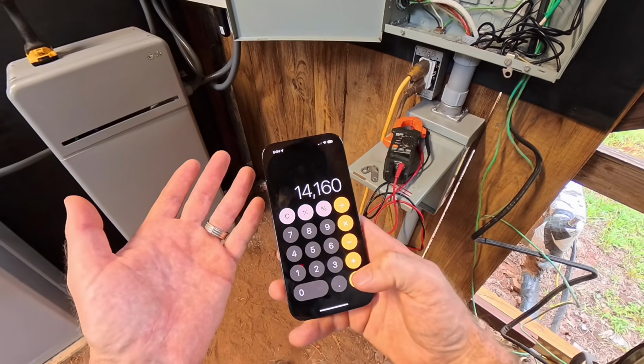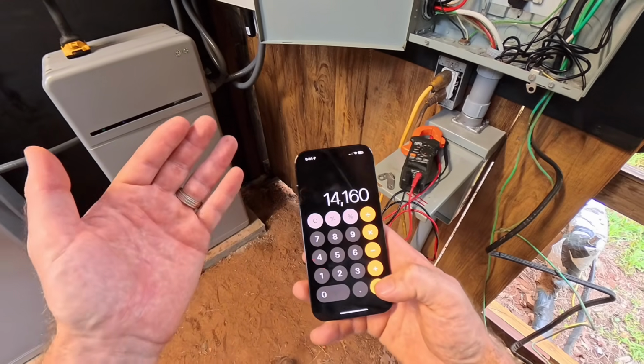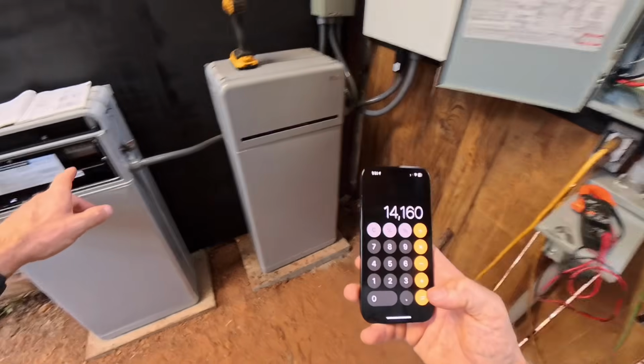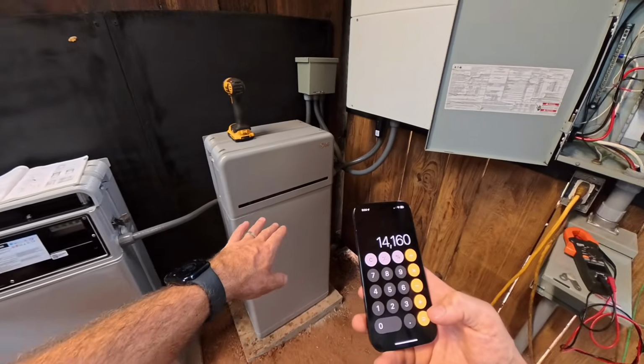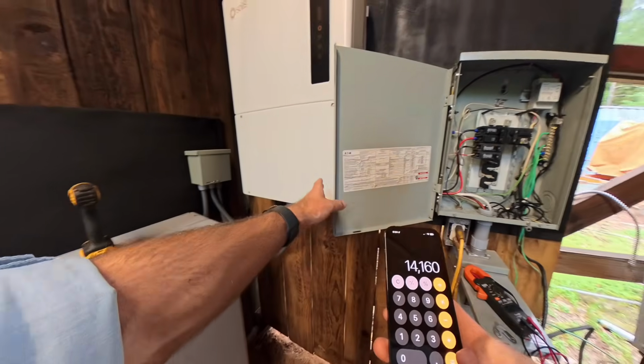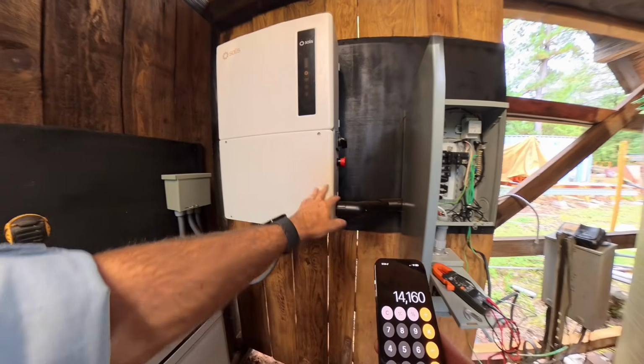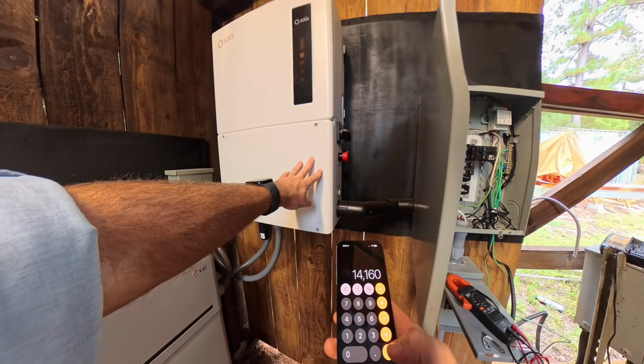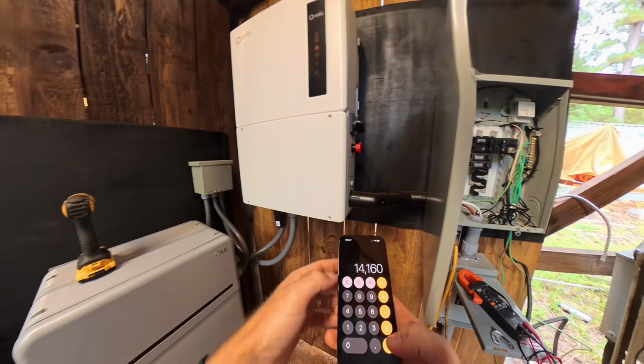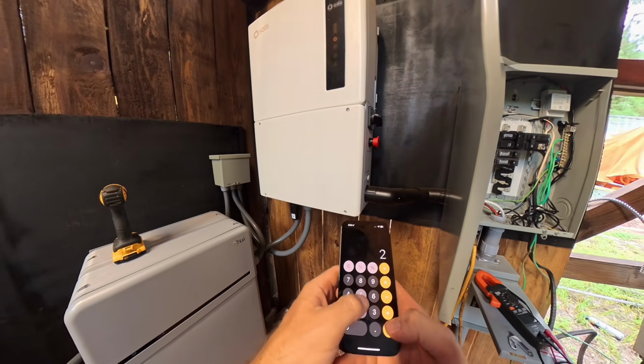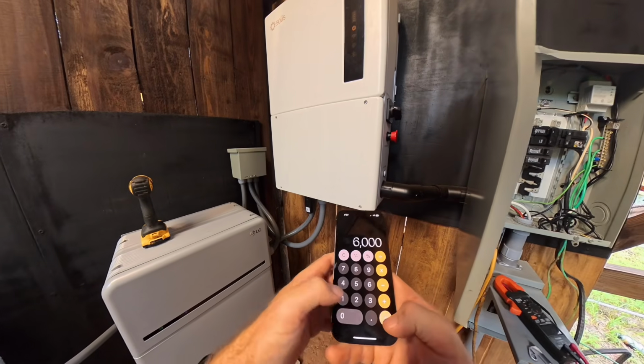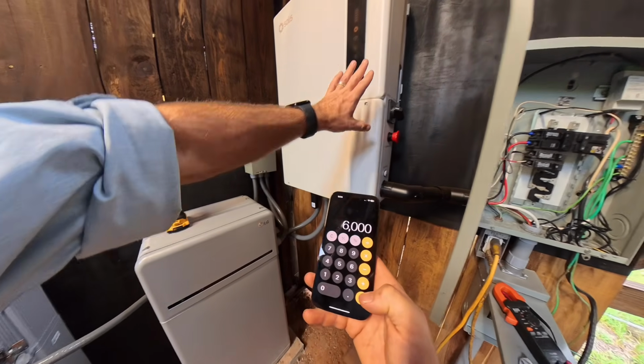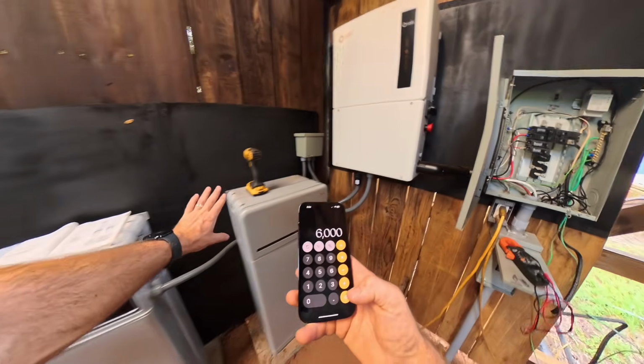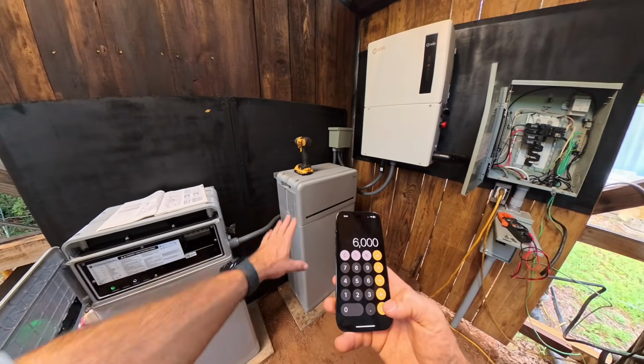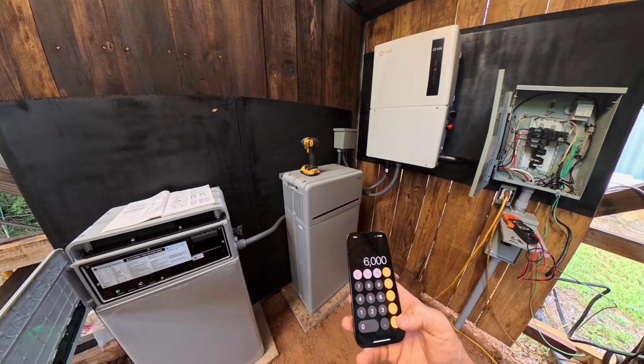If we look at that, we'll take 59 amps times 240, we're looking at 14,000 watts. Each of these are supposed to be able to put out 7,000 watts continuous. This is supposed to have a 20,000 watt, 30-second, I believe, start. And then the 25 times 240, 6,000 watts continuous. This can do 11,000 watts continuous. These can each do 7,000 watts continuous apiece.